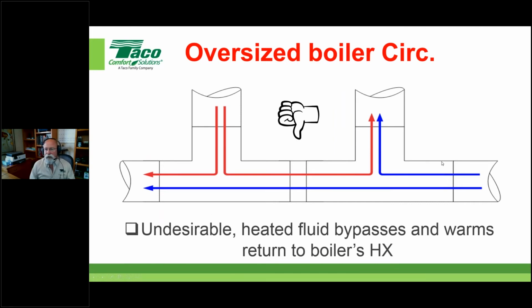Now I will admit that under these shoulder conditions, where you just have really not cold weather, just kind of sort of cold, maybe in the spring and in the fall, you're going to get this a little bit because, as I said before, even if you have a circulator that is controlled by the boiler, you can't go any lower than low. And the thing that we have going for us in those shoulder conditions is that they're nowhere close to a design condition, and so they're relatively short periods of time where we have this. And the cumulative temperature is still below that magic number of condensing. So I'm still condensing for the most part within those shoulder conditions.